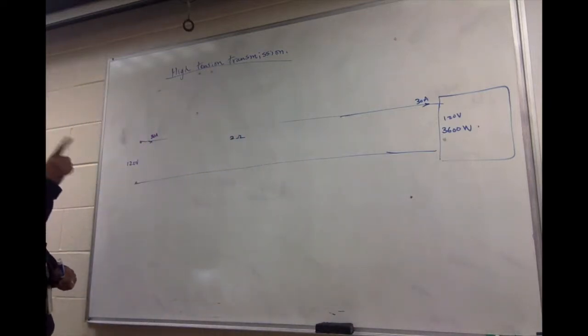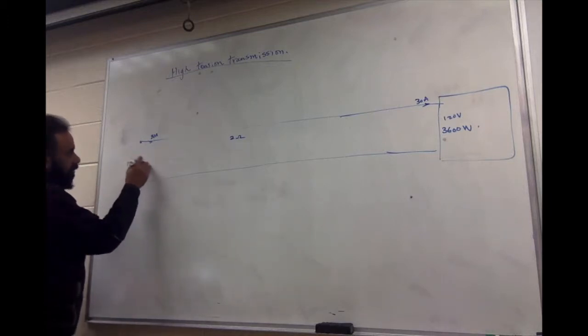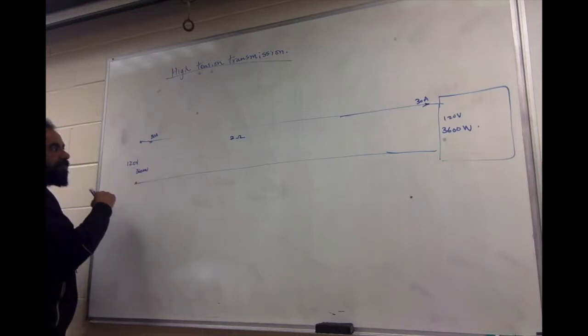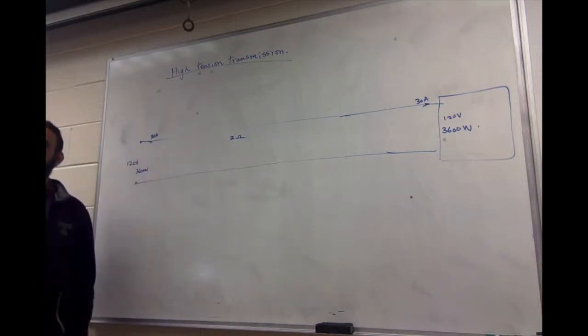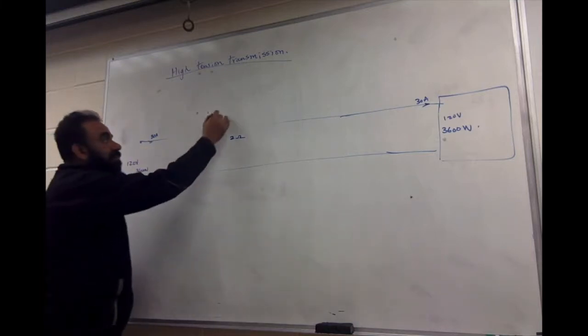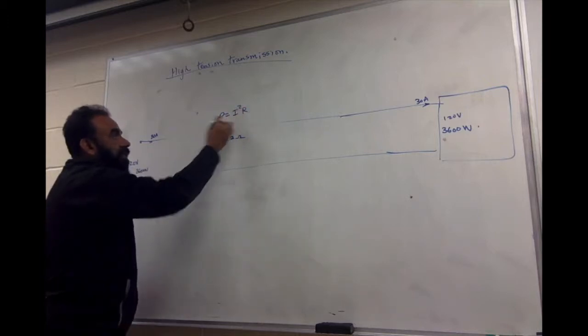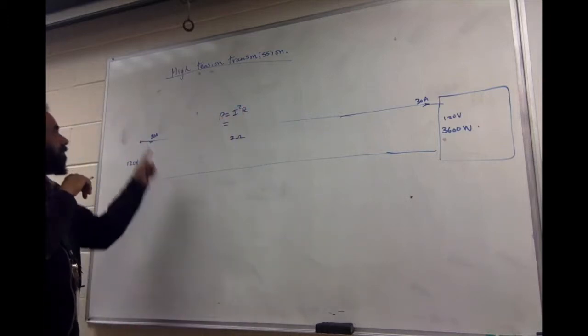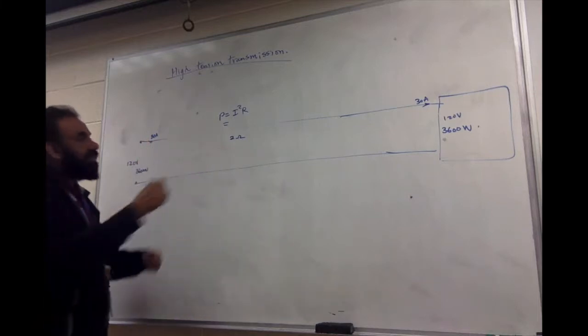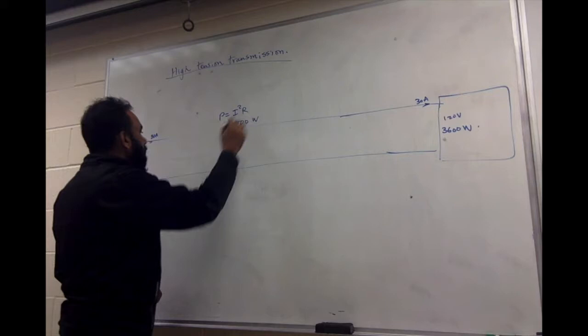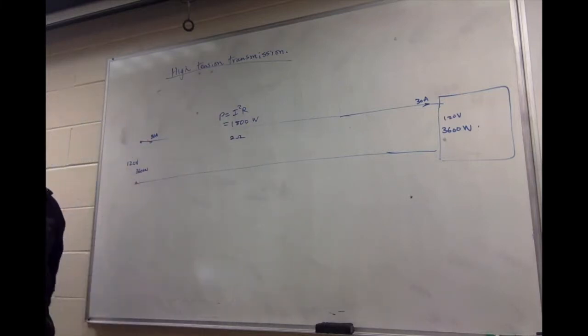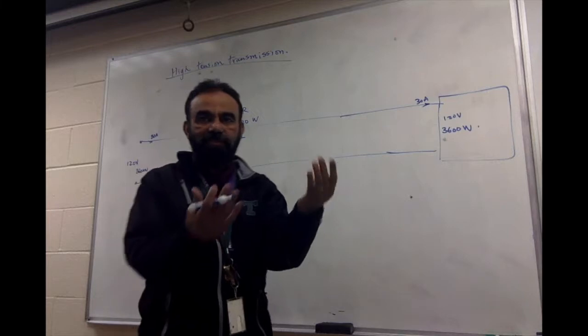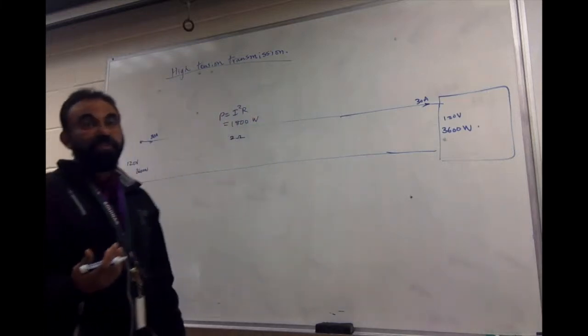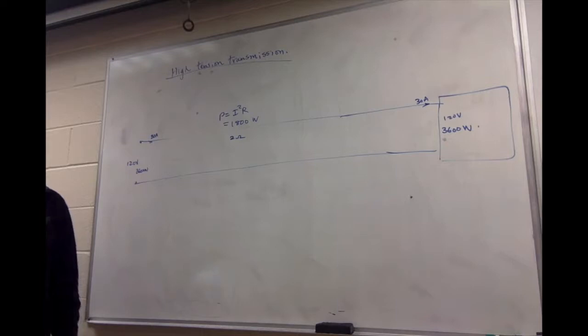Now 3,600 watts is what you want over there, but it's not going to reach 3,600. Let's look at the wattage. If this one is genuinely sending 3,600 watts, how much is the loss of power on the way? Power loss is I squared R. How much is the loss? 30 squared times 2, that's 1,800 watts lost out of 3,600. So you're only getting 1,800 watts of usage, which is not an efficient way of transferring energy, correct?